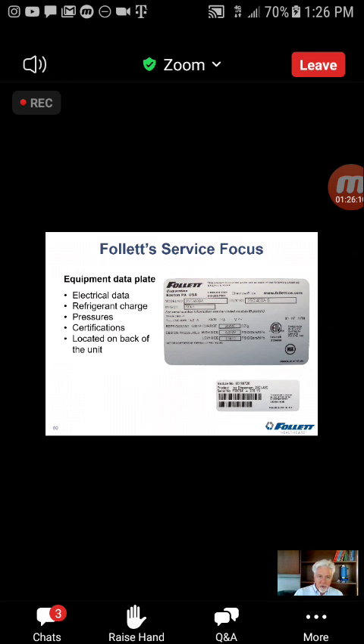The important one for the service tech is the little guy. This is your stock module identification plate. There are at least two of them on each unit. There is one on the back near the data plate, but there's also one on the refrigerators and freezers on the inside of the cabinet on the left-hand side near the product simulation bottle. So you don't have to pull the unit from the wall to get the serial number.